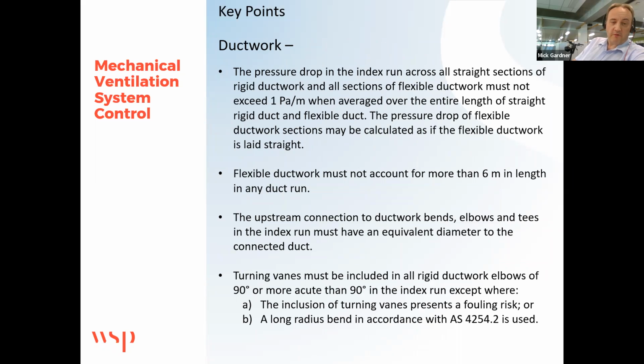Included within this are the new rules for ductwork. So your pressure drop across your index run has to be calculated, and you must not exceed 1 pascal per meter of pressure loss as you're sizing your duct, as an average over the entire length of the duct. Pressure drop for flexible ductwork sections may be calculated as if the flexible ductwork is laid straight. So we are assuming that when we are sizing this, the ductwork is laid nice and flat, not crushed like we sometimes get on site, and it's all been laid nice and perfect.